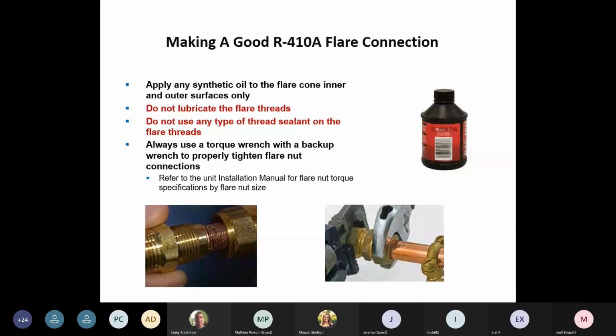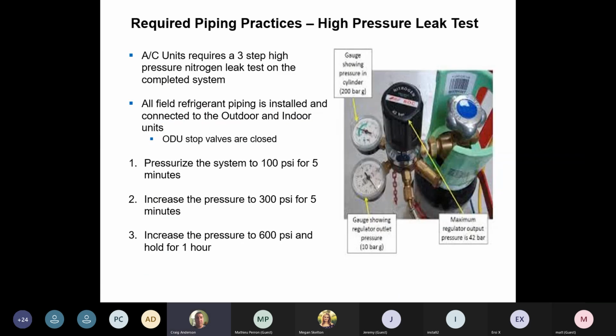Leak check. We call it a 3-step leak check. It's always been out there. It's always been in the manuals. What we want to do is a 3-stage. First thing, it's going to save you nitrogen out there in the field. If you've got a leak, crank it up to 100 PSI and hold it for 5 minutes. If it moves within those 5 minutes at 100 PSI, then you know you have your leak. If you threw the whole 600 PSI in there and you have a leak, you just lost all that nitrogen. Throw 100 in, wait for 5 minutes, bring it up to 300, wait for another 5 minutes. If it doesn't move, then crank it right up to 600.